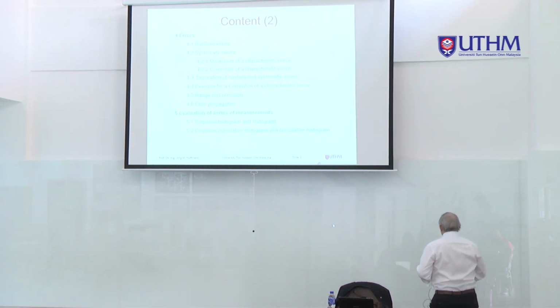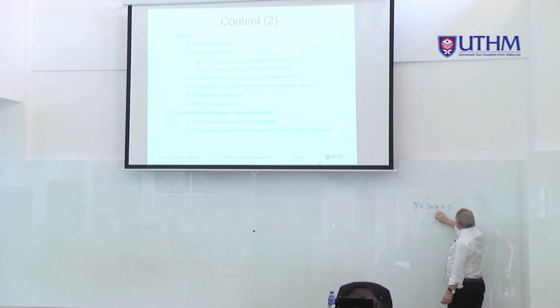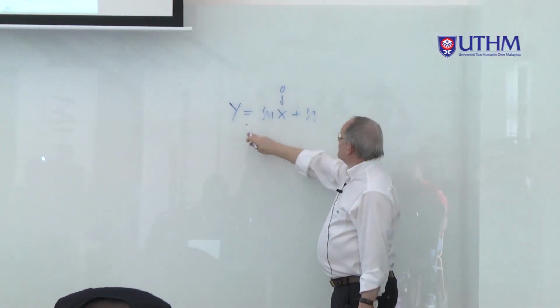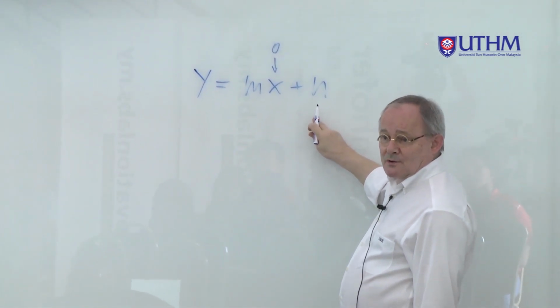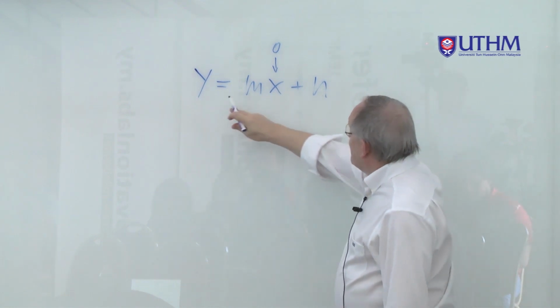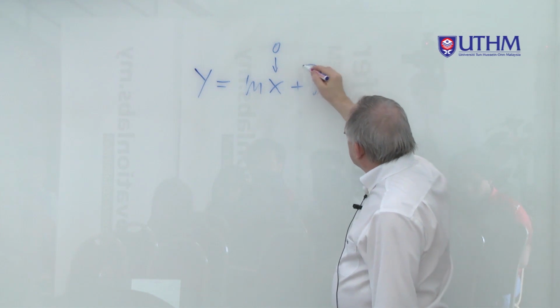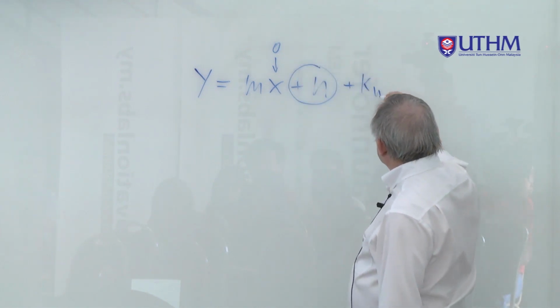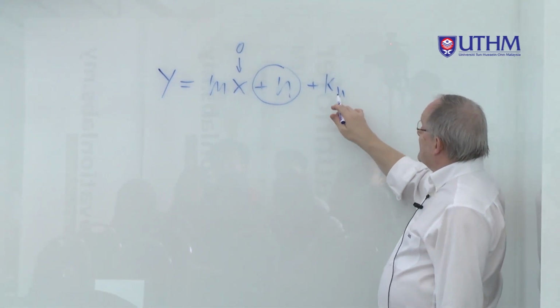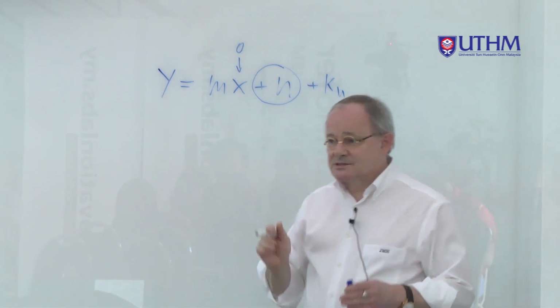When you stand on a balance, the balance should have a linear behavior. y = mx + n. This is the output side, that is the input side. When you put nothing on the balance, then m is unimportant, it's 0. When y is not 0, you know that n is not 0, and you know that's a mistake. And this mistake you have to correct, that you correct this plus n by a correction function, a correction number, plus kn, which has to be minus n, so that it is 0.